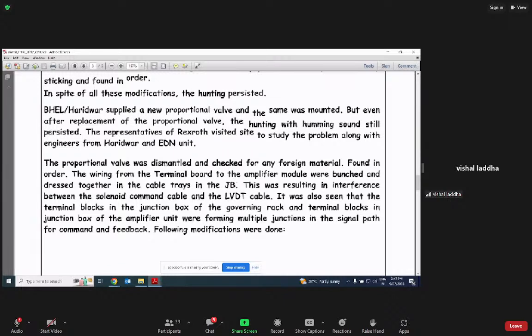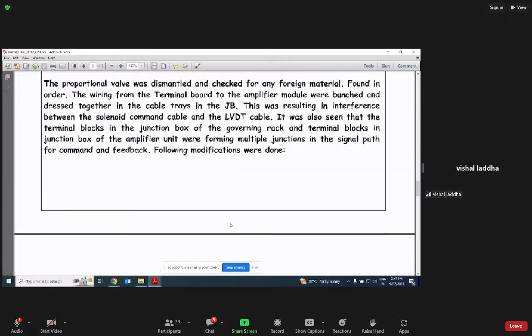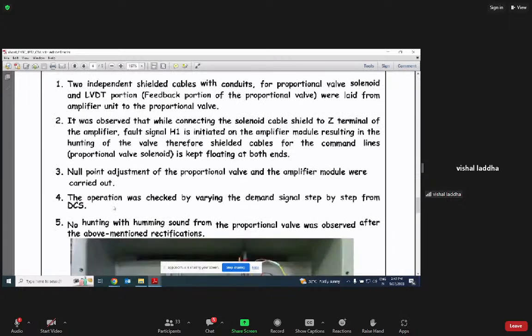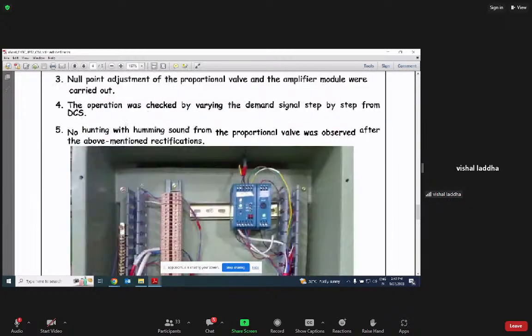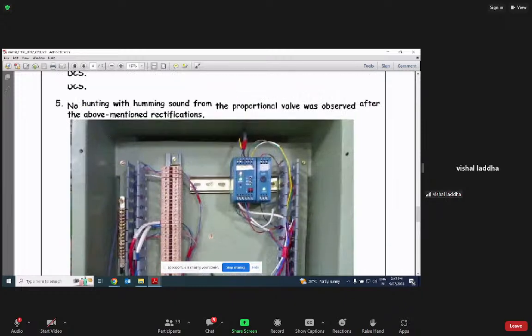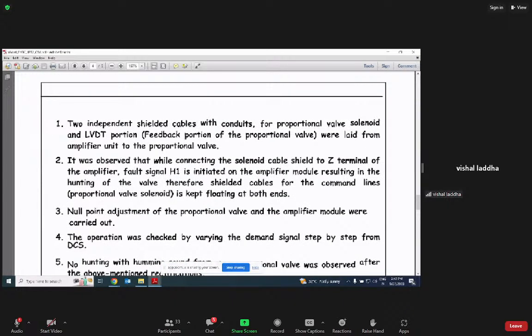It was also seen that the terminal block in the junction box of the governing rack and the terminal block in the junction box of the amplifier unit were forming multiple junctions in the signal path for command and feedback. The following modifications were done. These 5 modifications were done. You just check this JB. This modification was done. What modification?